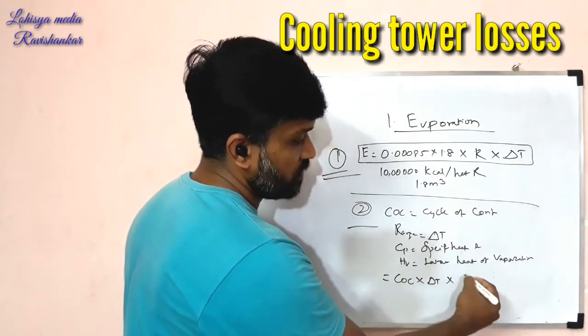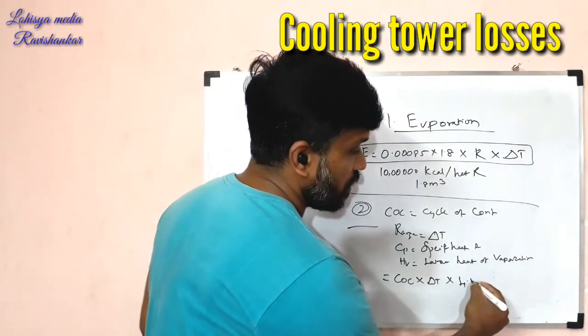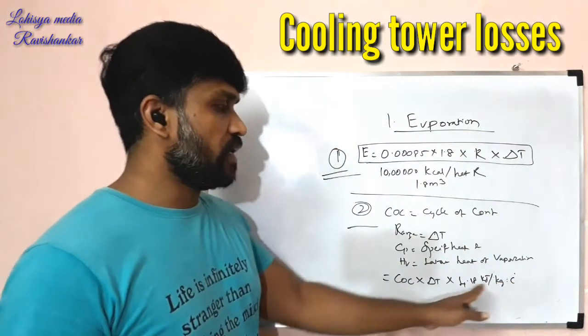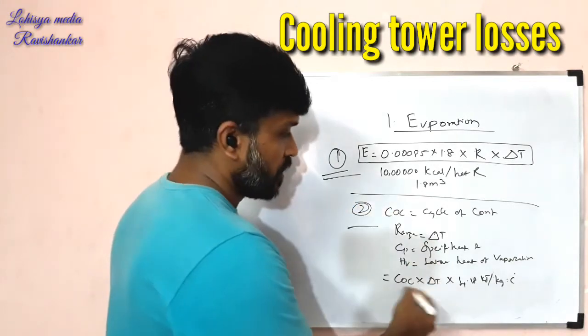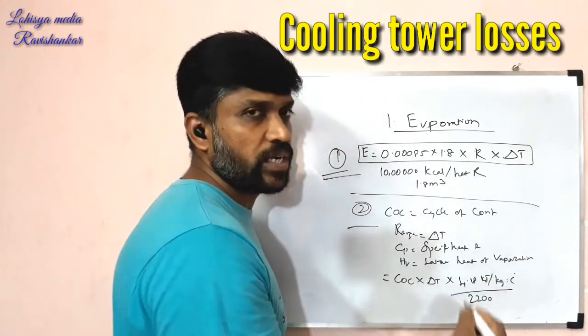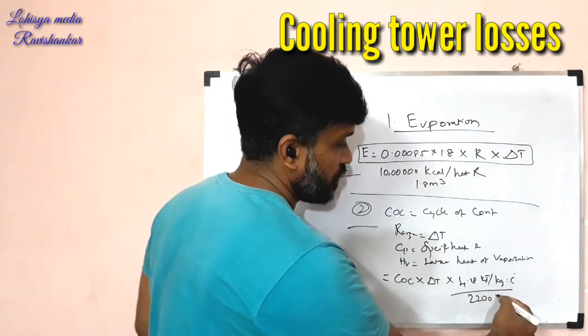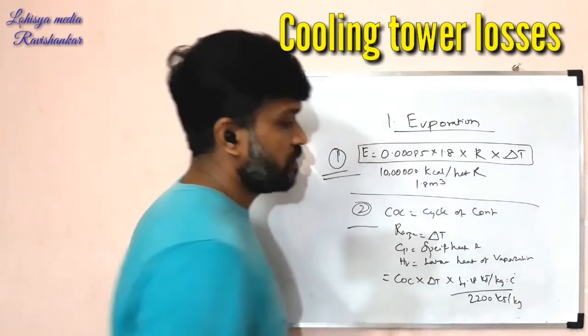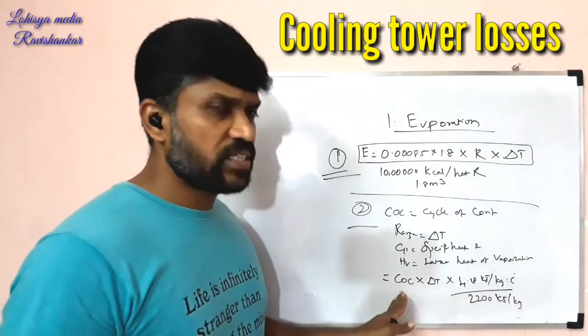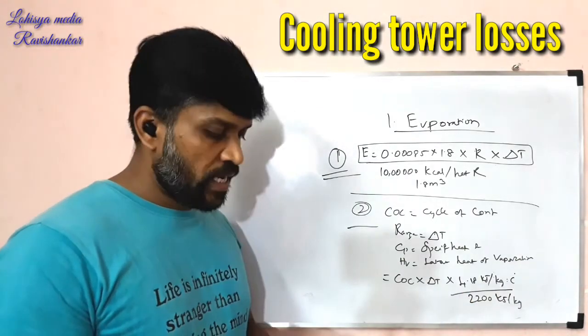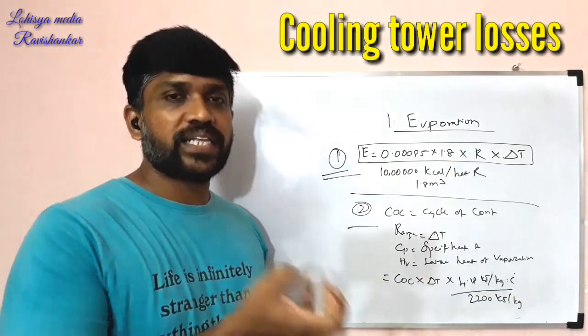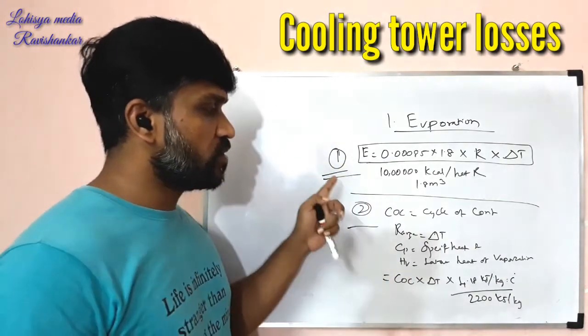CoC range, into Cp (specific heat of water) — this water value is 4.18 kJ per kg per degree centigrade. That is the specific heat of water. Divided by HV, the latent heat of vaporization, which is 2200 to 2260 kJ per kg. This is the HV value used with CoC and the range to calculate how much water will evaporate for a given heat rejection.